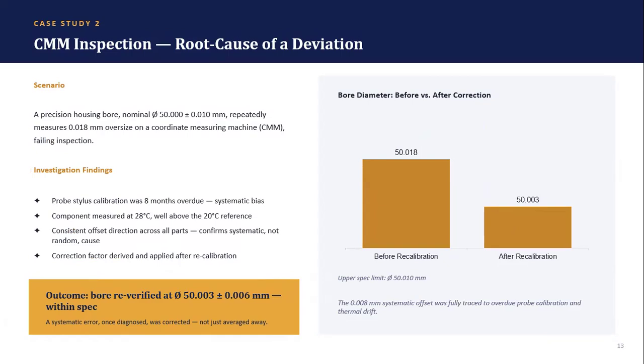Our second case study involves a coordinate measuring machine. A precision housing bore has a nominal diameter of 50 millimeter with a tolerance of plus or minus 0.010 mm. The CMM repeatedly measures the bore as 50.018 mm, which indicates an oversized condition. An investigation reveals two important factors. First, the probe stylus calibration was 8 months overdue. Second, the component was measured at 28 degrees Celsius rather than the 20 degrees Celsius reference condition. The consistent direction of the deviation indicates a systematic error rather than random error.